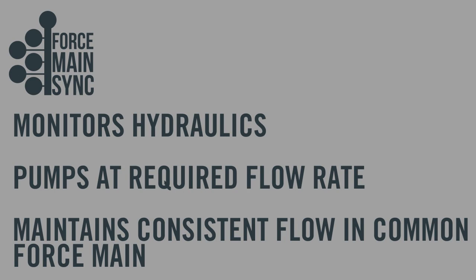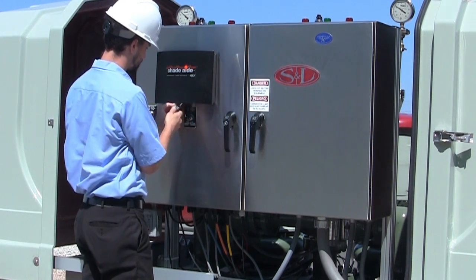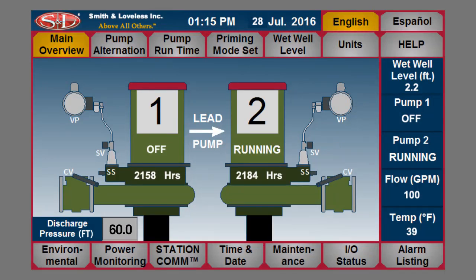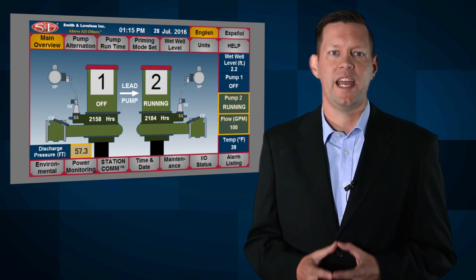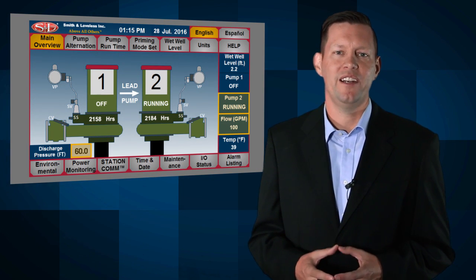All common force mains face extreme pumping conditions in attempting to maintain a consistent flow. Now, a simple computer program called Force Main Sync by Smith & Loveless can monitor the hydraulics in the common force main and keep the pump station pumping at the flow rate required to maintain a consistent flow. Drawing upon vast hydraulic and pumping system design expertise, Smith & Loveless engineers developed Force Main Sync to continually read the force main's condition and simply adjust pump speeds to meet the changing flow conditions. This is in comparison to the traditional answer of an oversized pump station providing variable flows, which have very inefficient pumping rates.